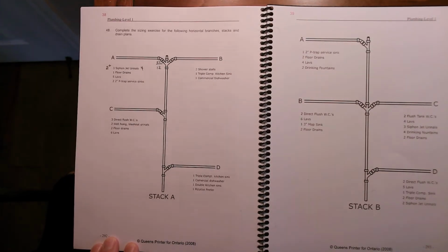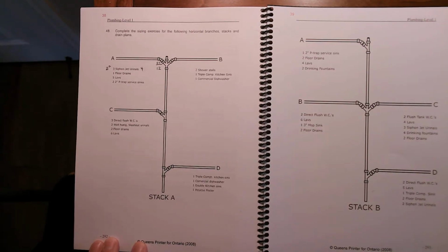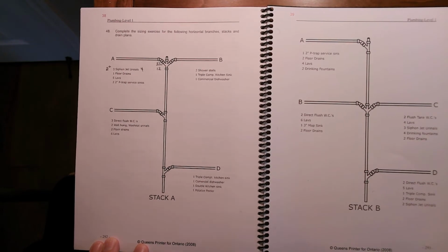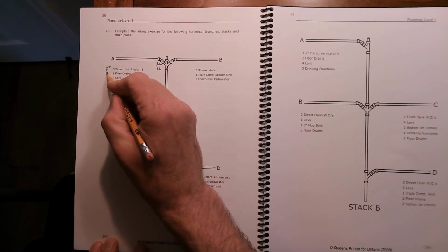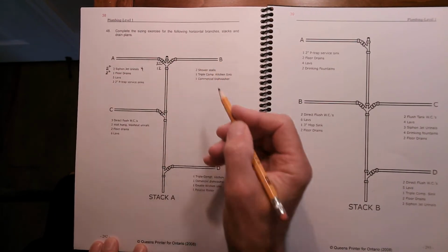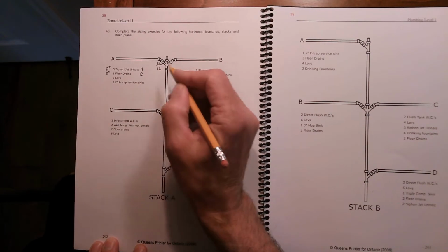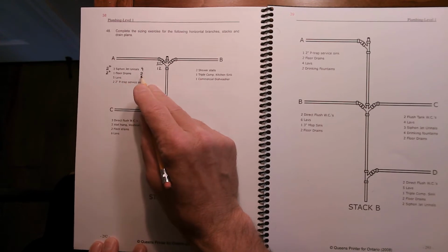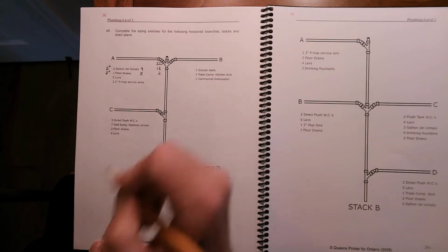Good enough. The next one we're going to go to is floor drains. You take a look at floor drains. It is item number 15 on your list. And the smallest one there, which is what we use unless I ask otherwise, the smallest one is also 2-inch. And they are 2 fixture units each. But there's only one of those at 2 fixture units, so the total fixture units for floor drains is 2.